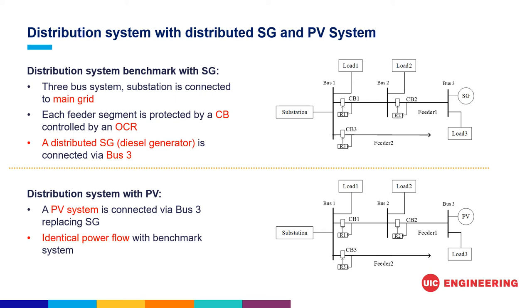To formulate the full scenario, we designed a distribution benchmark with a distributed synchronous generator. This system is connected to the main grid, and each feeder segment is protected by a circuit breaker controlled by an overcurrent relay. A distributed synchronous generator is connected through bus 3 — this synchronous generator is a diesel generator. To study the impact of PV generation on this protection system, the synchronous generator is replaced with a PV system. This new system shares the identical power flow with the benchmark system.